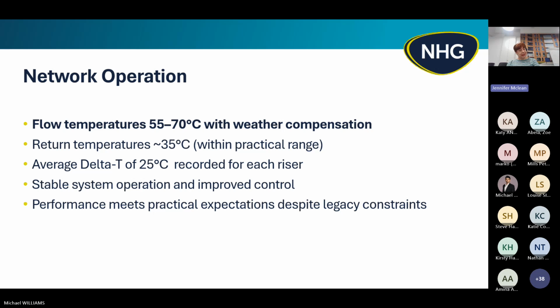So, as mentioned earlier, we have good flow temperatures across the system with weather compensation. The return temperatures are around 35 degrees Celsius, and on average a delta T of around 25 degrees for each riser. So it's a much more stable system with improved controls, and essentially the performance meets the practical expectations of what we expected to deliver through the works. But the funding, the grant funding that we received. Next slide, please.